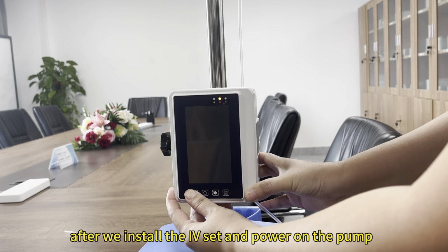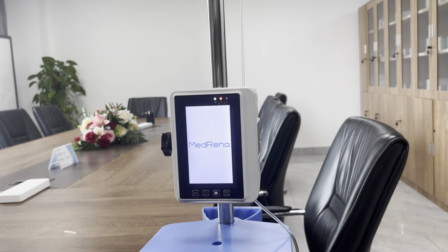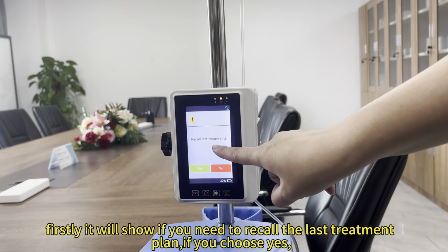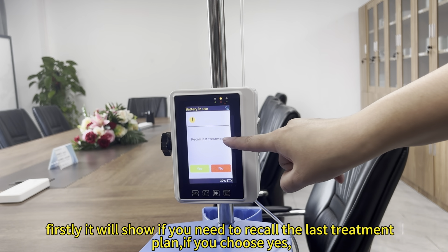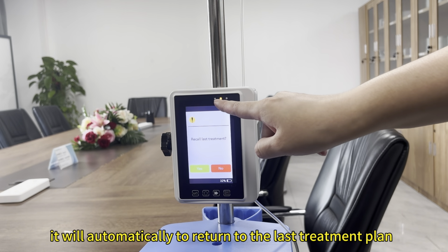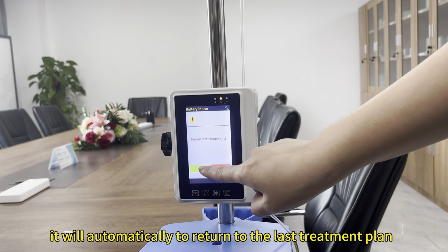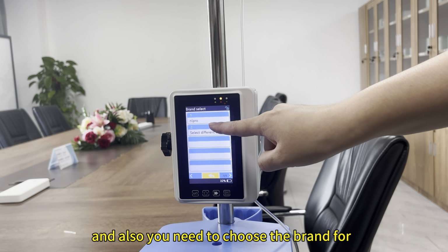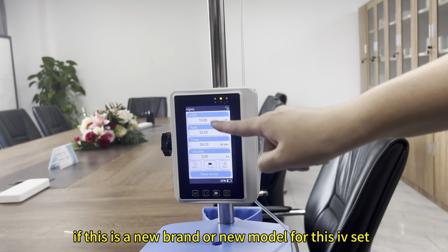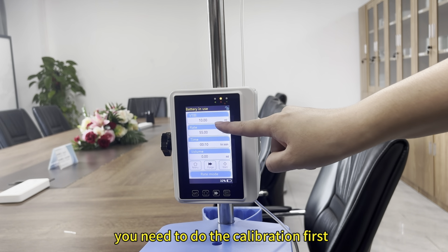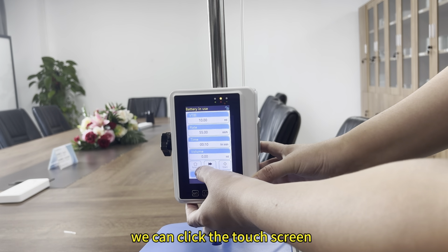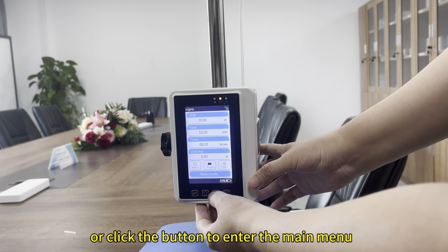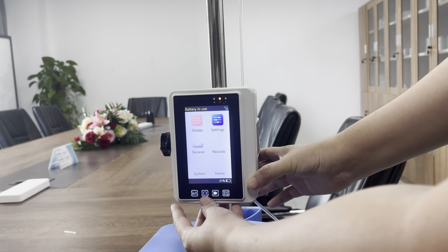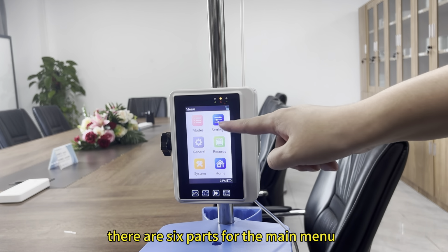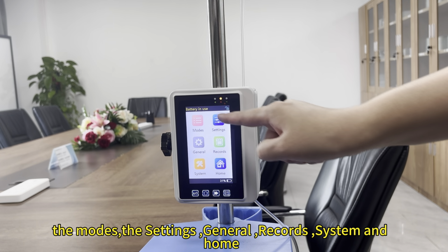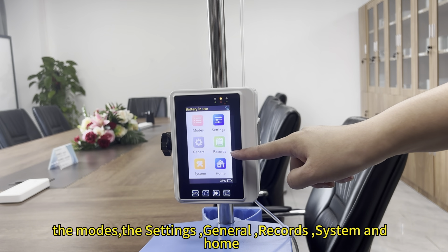After we install the IV set and power on the pump, firstly, it will ask if you need to recall the last treatment. If you choose yes, it will automatically return to the last treatment plan. And you also need to choose the brand for this IV set. If this is a new brand or new model of IV set, you need to do the calibration first. We can click the touch screen or click the button to enter the main menu. There are 6 parts in the main menu: modes, settings, general, records, system, and home.